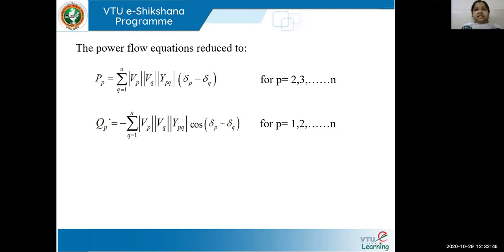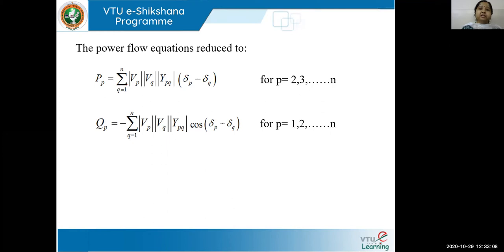These two equations become decoupled and need not be solved simultaneously — they can be solved sequentially. Since the solution is non-iterative and the dimension is reduced from 2n to n−1, it is a computationally highly economical solution. This is all about the approximate load flow solution.